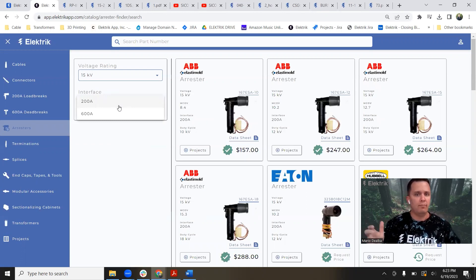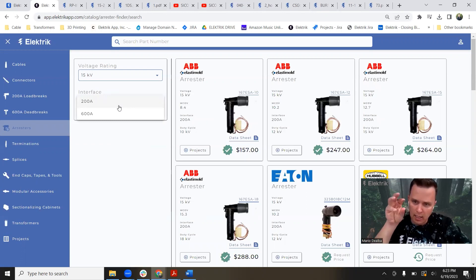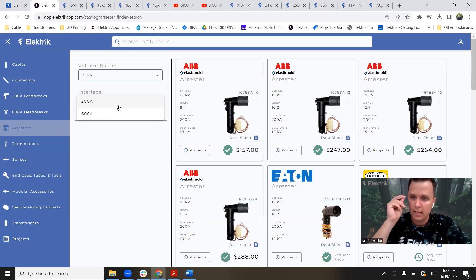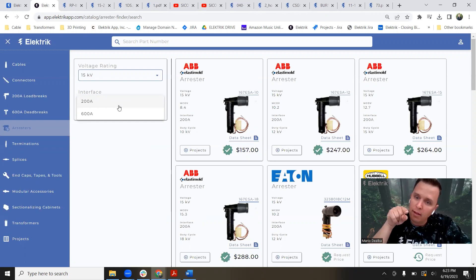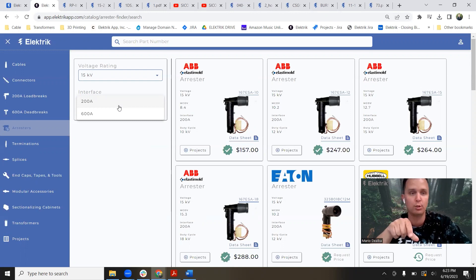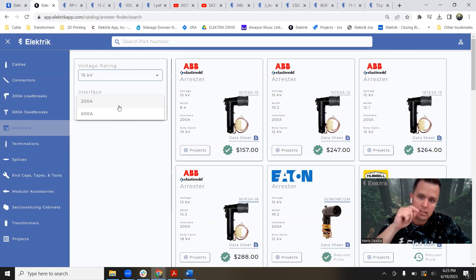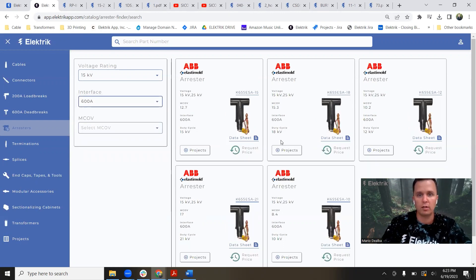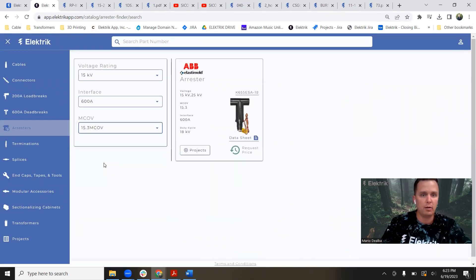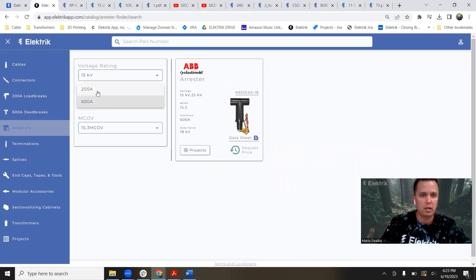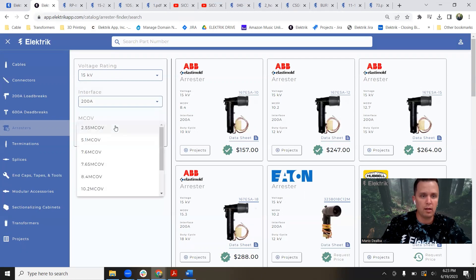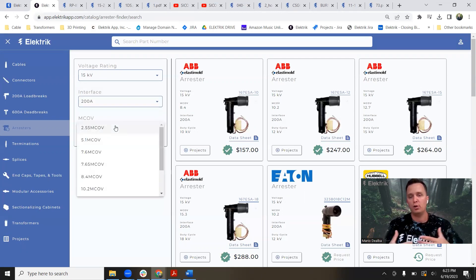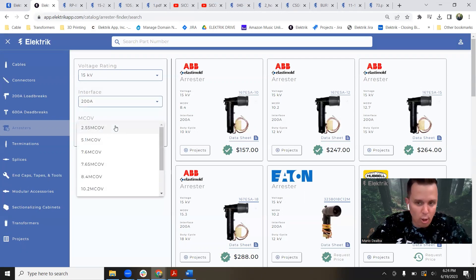If you have a bushing and it looks red, that's 15 kV — that's the first sign. Then if it looks like something you slide on, that's a load break bushing. If it has threads, that's a dead break, which would be a 600 amp. So a 600 amp dead break would look like this, and a 200 amp load break would look like this.